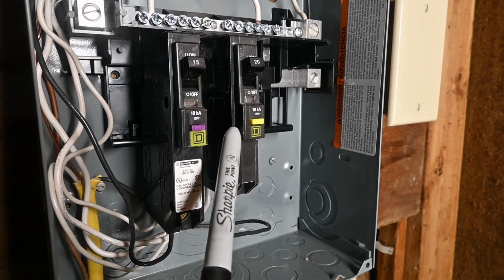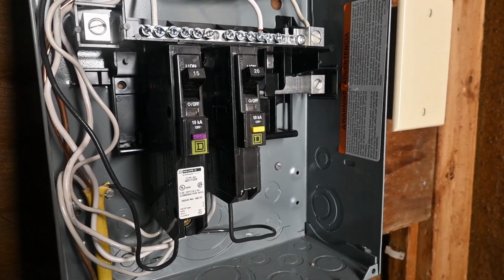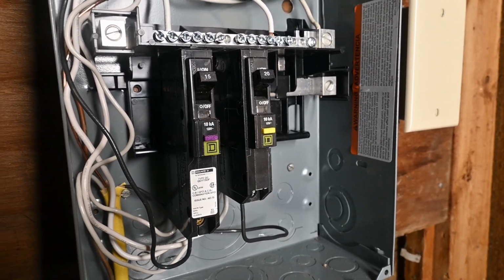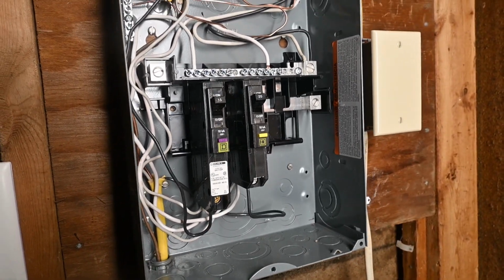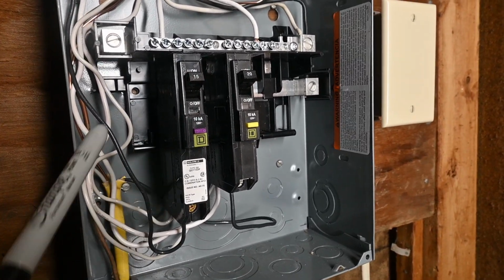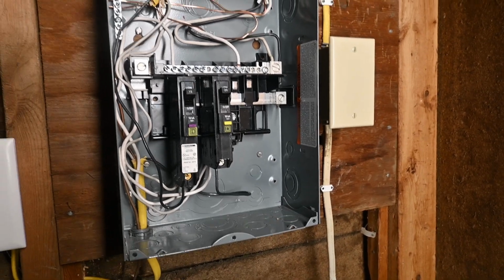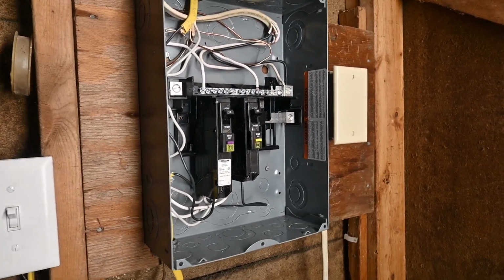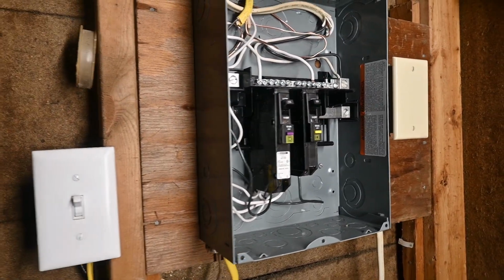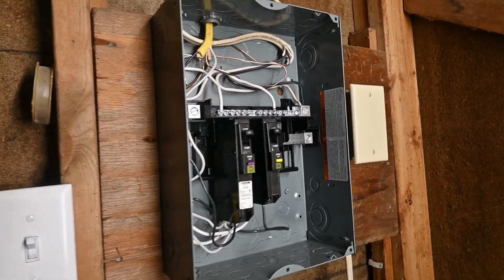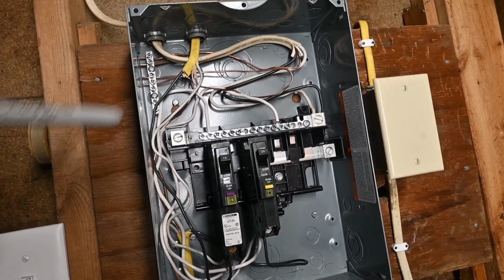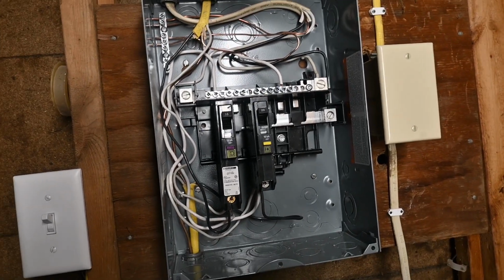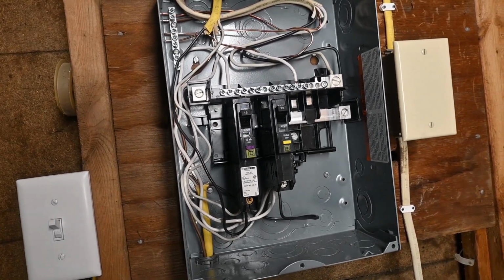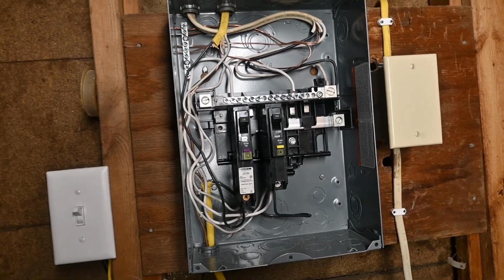And this one is just a ground fault breaker. So all of the circuits in this garage are protected by ground fault, and then one of them is protected by arc fault. Arc fault is optional in garages, but ground fault is required for any receptacles. So this is a pretty safe and quality installation, albeit it's not the most organized, but it really doesn't have any glaring safety issues that I can see. So let me know if you saw anything that is a terrible safety consideration.